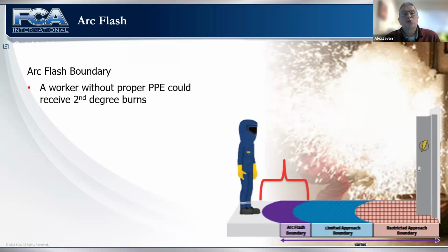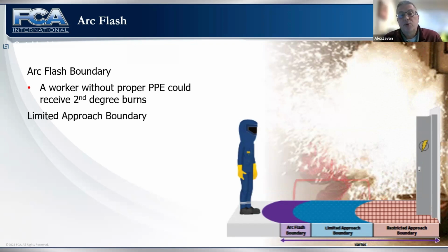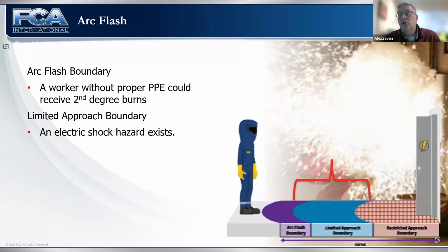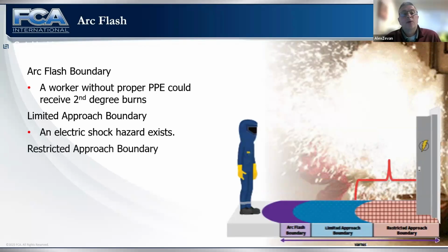The arc flash boundary is where a worker without proper PPE could receive a second-degree burn. The limited approach boundary is the next area, where an electrical shock hazard exists, and only qualified people are allowed in this area. The restricted approach boundary is only for qualified workers. You would not allow just anybody to cross that barrier without knowing what they're doing and why they're there.